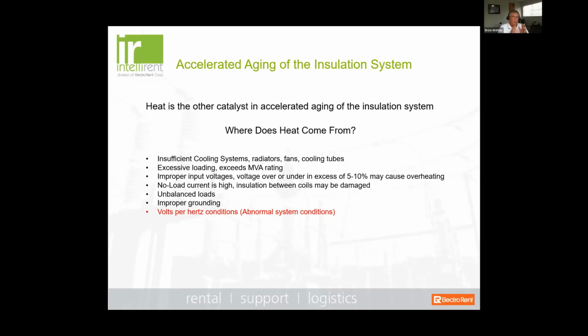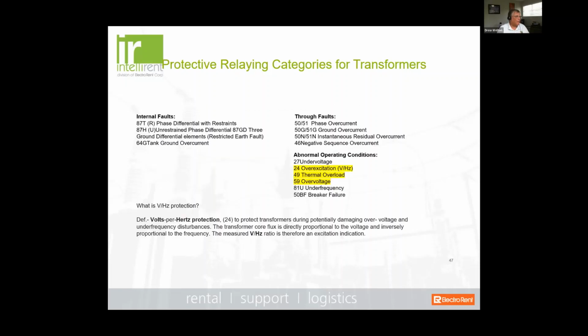But one of the things we want to look at is also what's called a volts per hertz condition. Okay, and this is typically referred to from PSRC, Protective Relay and Controls Subcommittee, as abnormal system conditions. Okay, and if we look at our protective elements associated with heat in transformer protection, you've got your overexcitation, a thermal overload, and then overvoltage. All three of these conditions can cause excessive heating, and then will protect the transformer from that happening if enabled properly.